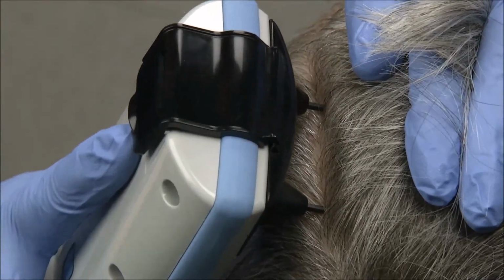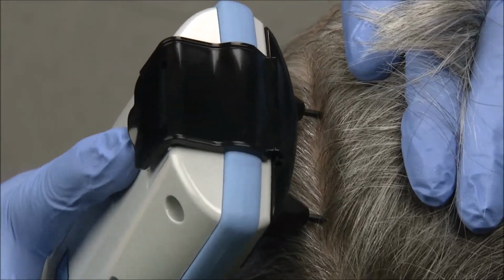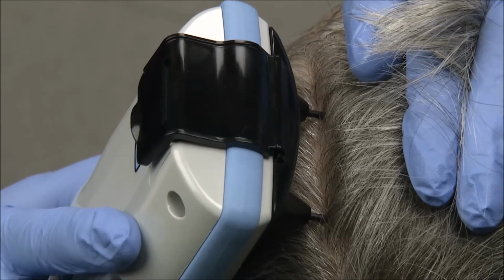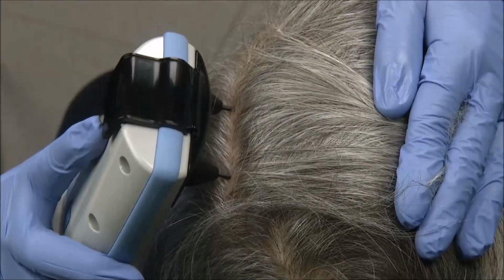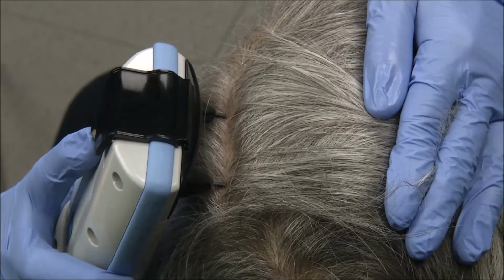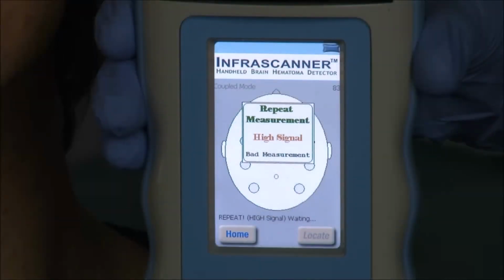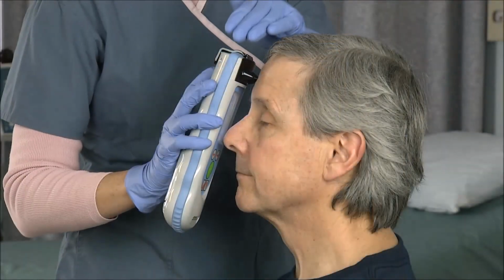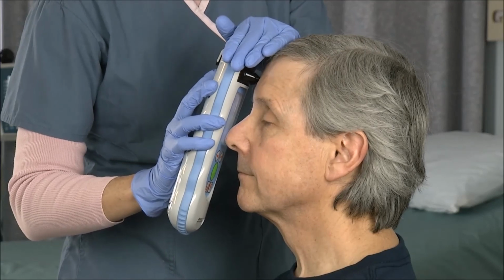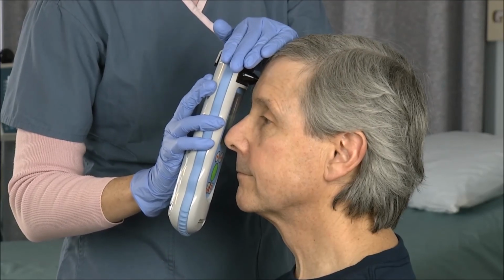Gray hair has little pigment. This makes the probe tips easier to see when parting the hair, especially on light skin. Make clean parts and use the wiggle technique. Since gray hair lacks pigment, it is highly reflective. This could cause the infrascanner to give off a high signal error message. If this occurs, use the shielding technique to reduce ambient light and scan again.